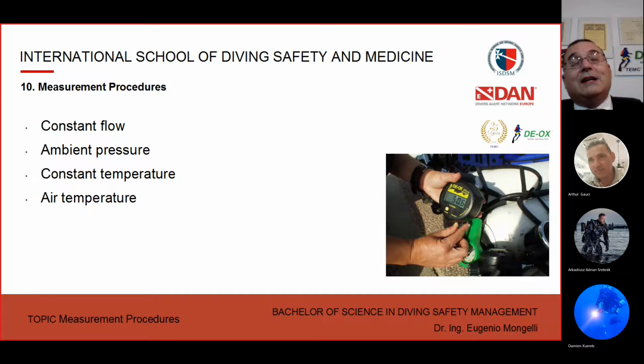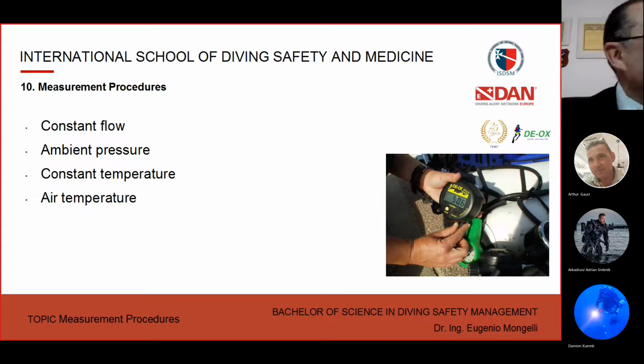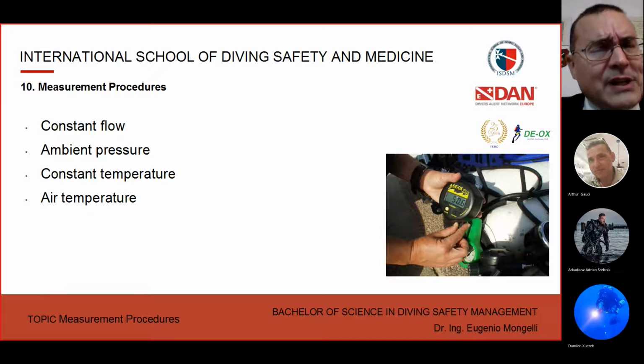So this is why, when you are in a high temperature environment, you need to have the sensor at the same temperature as the gas, both calibrating and analyzing. Okay, the target gas that you are going to analyze. This is extremely important, and this is the most common source of error of the analyzers, because maybe the analyzer was left under the sun, the sensor is hot, so you make a calibration with a hot sensor, and then you pretend to analyze a dive cylinder that is at a lower temperature. Understand? This is extremely important, because this may also give you 1, 2, 3% of inaccuracy.